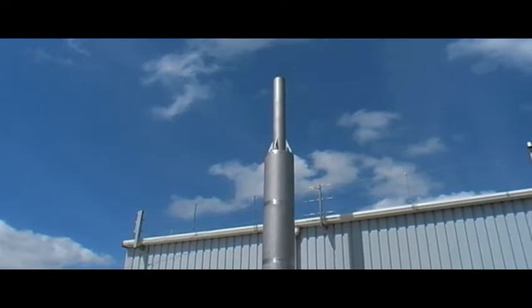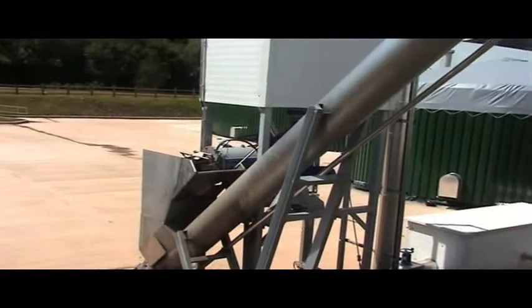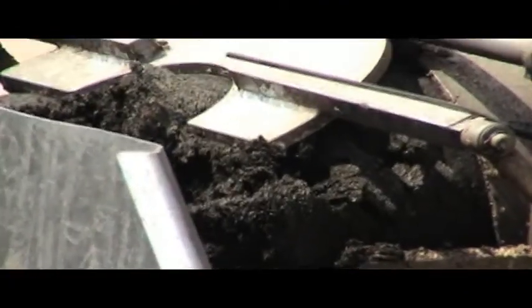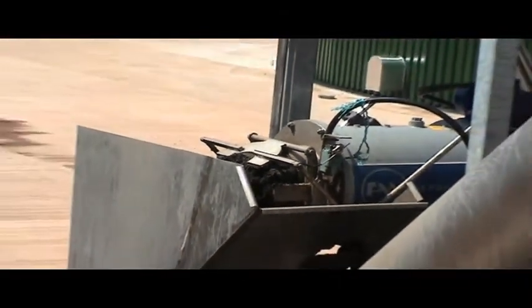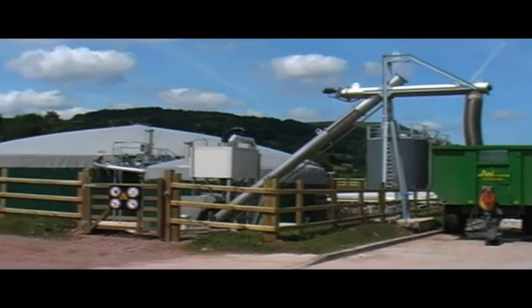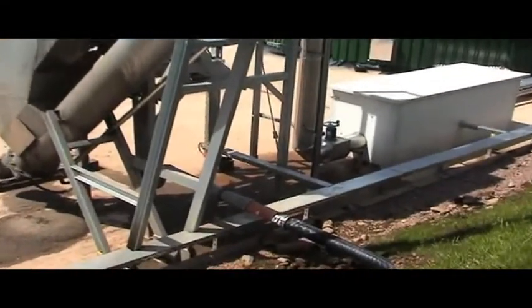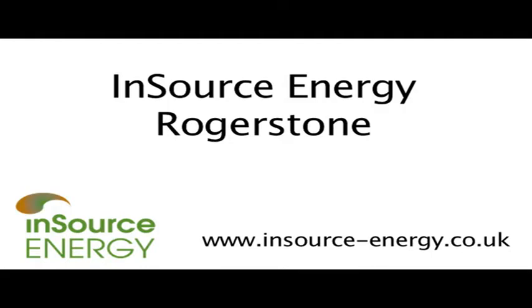The digestate itself from the anaerobic digester is pumped forward from the small four-day residue tank to a separator, which is essentially a screw press that separates out the fibre from the liquid in the digestate. The solid fraction is transferred using a series of screw conveyors into an agricultural trailer, which is then removed to replace chemical fertilizers for arable crops. The liquid fraction from the separator passes directly to sewer through a V-notch weir, which is monitored by Welsh Water.